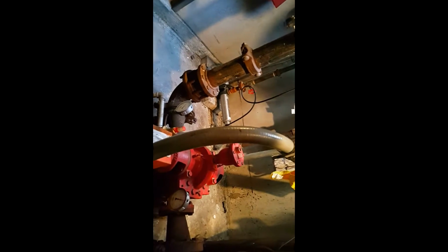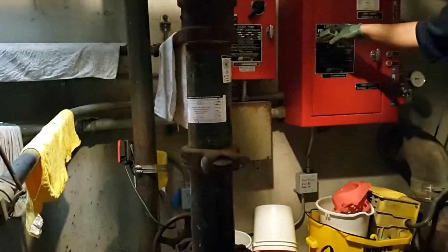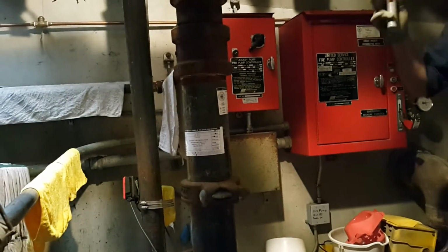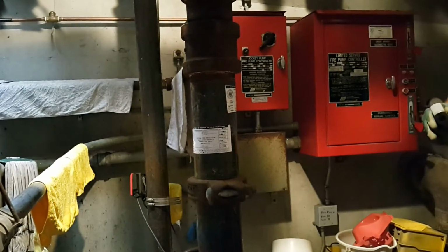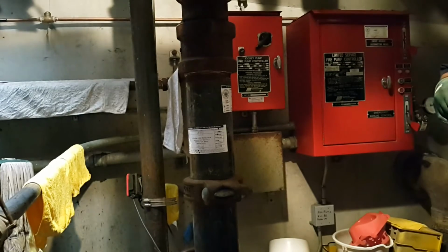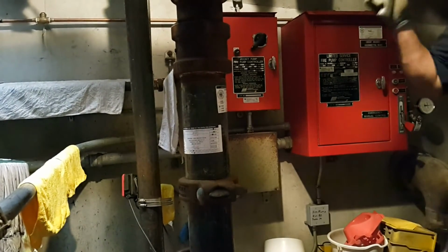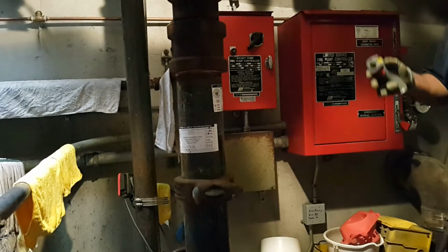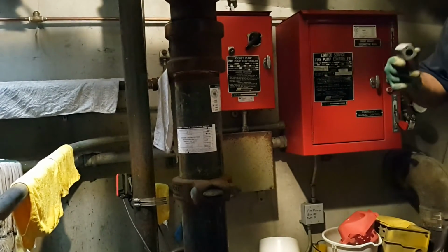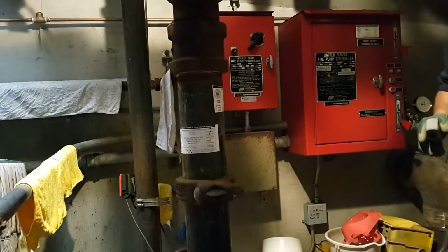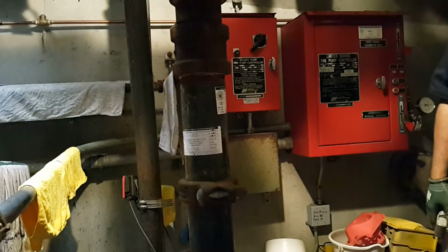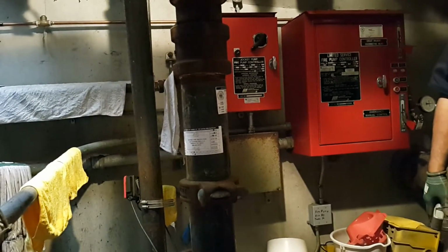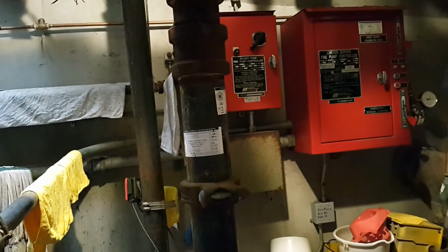Same thing when you do all your checks on your panels. Say you have a water surge or something happens that there's demand for the fire pump. It'll run for 10 minutes and then it'll turn off. The City of San Francisco doesn't want that. For example, if in the middle of the night it comes on for whatever reason and there's no real emergency, they want you to come in and manually turn it off.